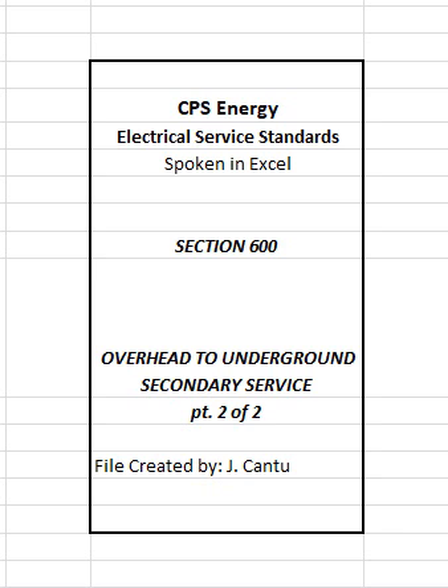Modular metering equipment shall be approved by CPS Energy as meeting CPS Energy standards and specifications. Customer shall coordinate the review and approval of modular metering equipment with the CPS Energy Customer Service Representative, refer to Section 1800. B. Independent main disconnecting device. At the line side of customer furnished and installed main service disconnecting means, device, where installed ahead of an auxiliary gutter supplying metering equipment. Customer's main disconnecting means shall be provided with lockable and sealable means.